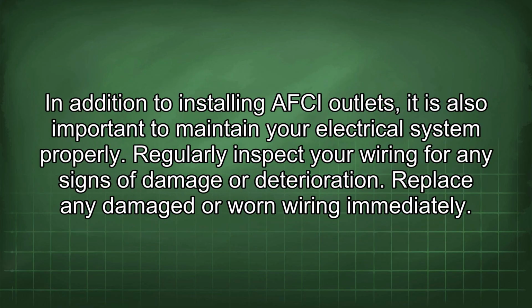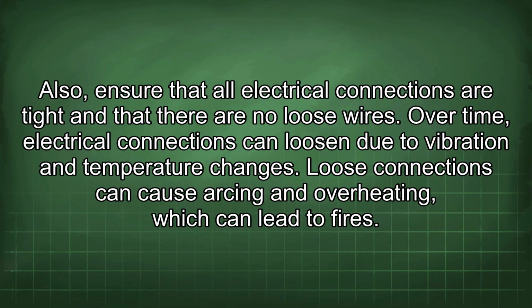In addition to installing AFCI outlets, it is also important to maintain your electrical system properly. Regularly inspect your wiring for any signs of damage or deterioration. Replace any damaged or worn wiring immediately. Also, ensure that all electrical connections are tight and that there are no loose wires. Over time, electrical connections can loosen due to vibration and temperature changes. Loose connections can cause arcing and overheating, which can lead to fires.